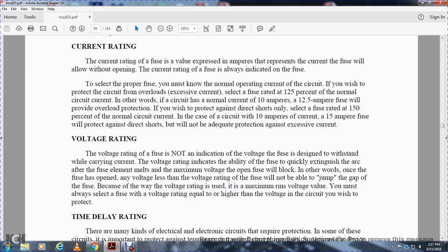Voltage rating: the voltage rating of a fuse does not indicate the voltage it is designed to carry current at. The voltage rating indicates the maximum voltage that an open fuse will block. In other words, once a fuse has opened, any voltage less than the voltage rating - the fuse will not be able to jump the gap. You must always select a fuse with a voltage rating equal to or higher than the voltage of the circuit it is to protect.